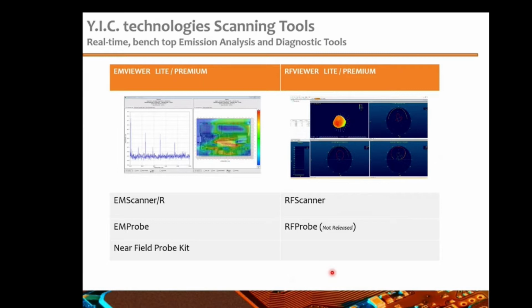The difference is our scanning technology. It's essentially an array of 1,218 or something like that probes, and the near-field probes, the robotic, the high resolution. I will review them later on. But the key factor here is the software, the EM viewer. All the instruments, including the near-field probe, can be connected to the same software, integrated. Everything is integrated within the EM viewer, including a camera, and that actually provides a real benefit for the user, and you will see that.